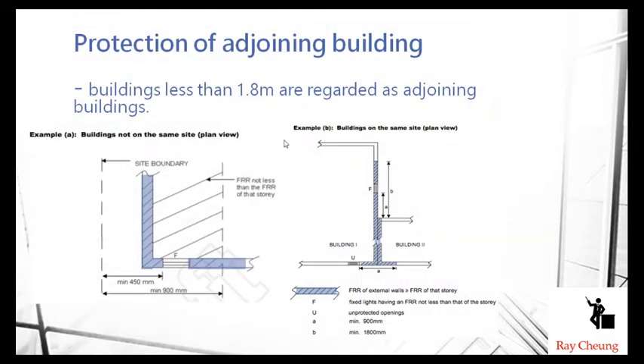Another requirement is protection against adjacent buildings. Normally, we consider a building to be adjoining if it is within 1.8 meters of another building. If two buildings are that close, we need to provide fire-resistant wall protection — a fire-rated wall between them.